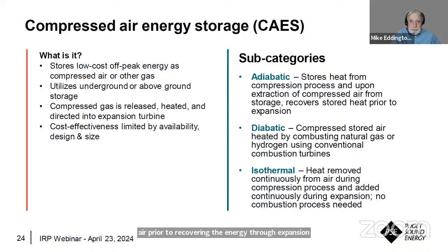The diabatic compressed air energy storage does not save the heat of compression, but it heats the air that's coming from the cavern prior to expansion by burning something like natural gas, or possibly a hydrogen fuel could be used, either in conventional combustion turbines, which provide exhaust heat, or through different stages of combustion ahead of the expansion turbines that drive the generators.